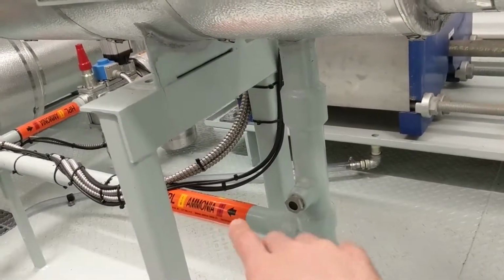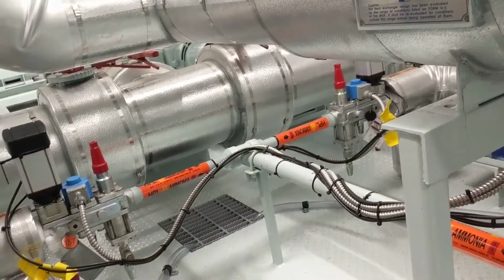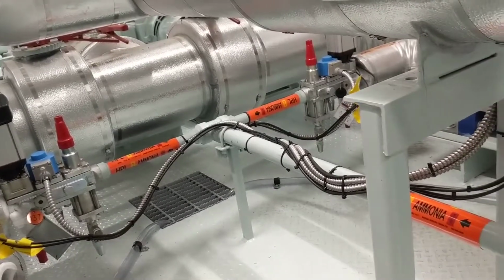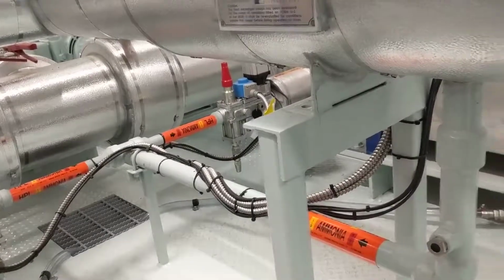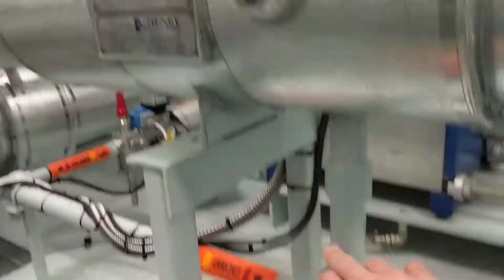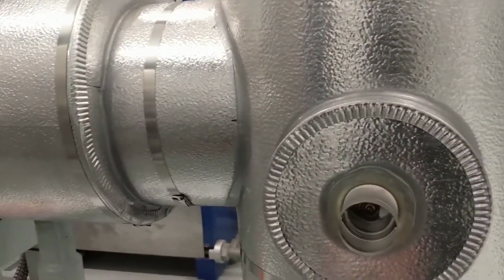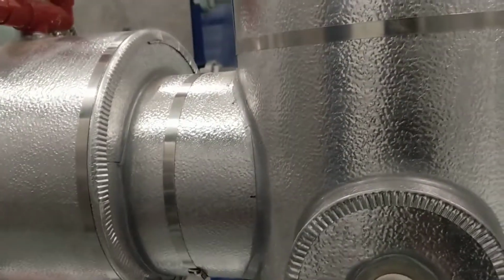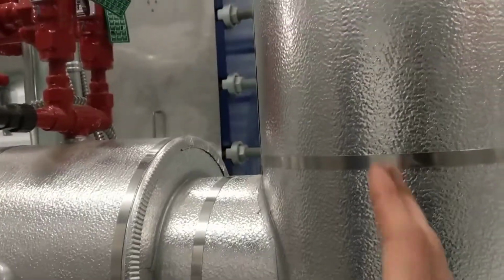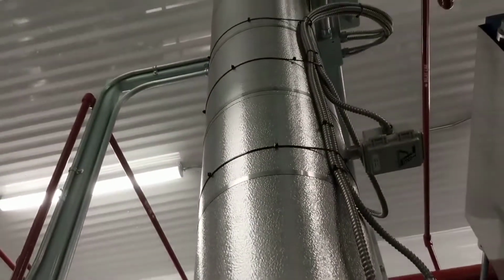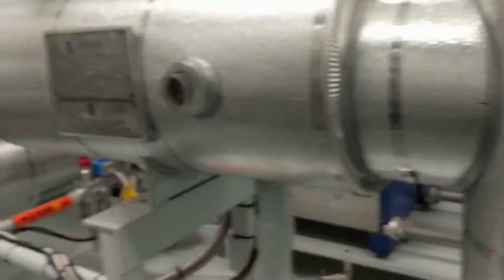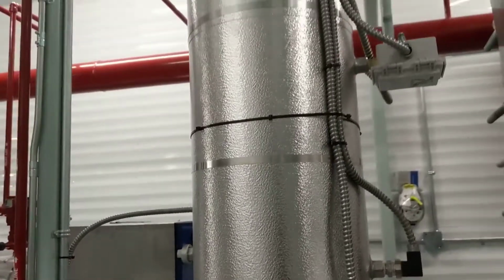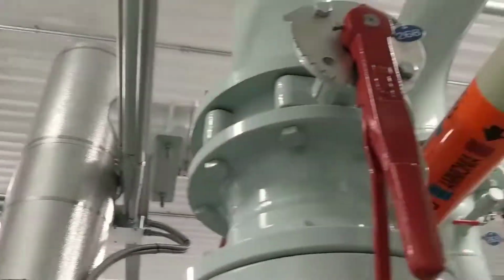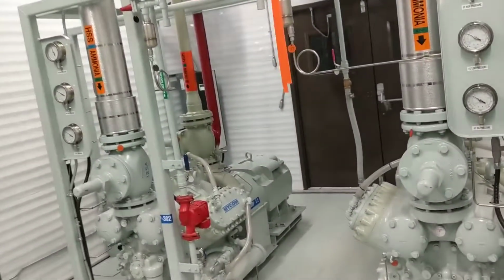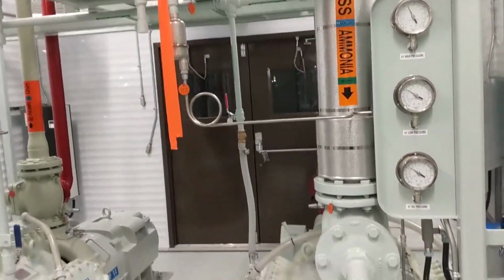As you can see from that label there, it's flowing this way over to the two TX valves, and that is why you've got ammonia in this sight glass here and in these sight glasses down here. But if you look over at this sight glass here, you don't have any ammonia in that. And the reason for that is because this part is where the ammonia is going out to the compressors, and it is low pressure vapor. So in here, you're not going to have liquid ammonia, because that's what's feeding the compressors with ammonia vapor for them to compress and turn into high pressure, high temperature ammonia.